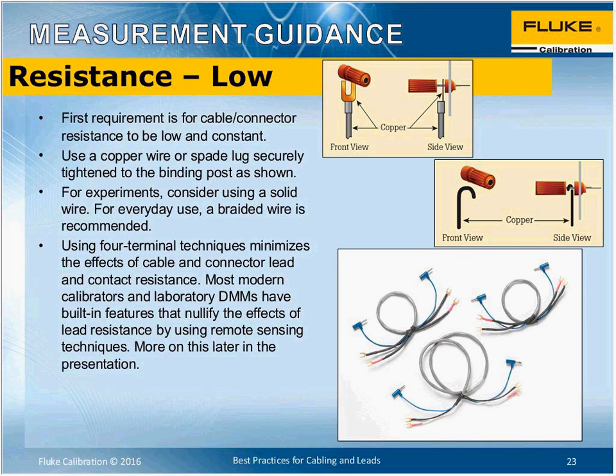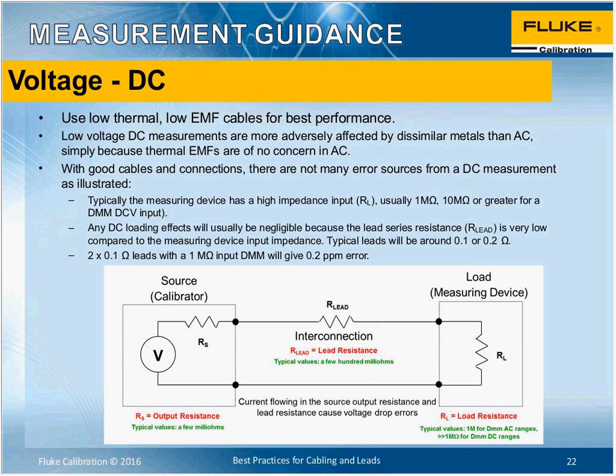But Rich, may I just come in there for a second? Yes, please. Apologies, Paul. There is one thing that occurs to me there. We illustrated that with a calibrator, but if, for example, you were using a voltage divider, it would possibly have quite a high output impedance of tens or even hundreds of kiloohms. The situation might be rather different, but in that case your measuring device would be the dominant impedance. So watch out if you have that situation, and think a little more about what the overall impedance and loading effect is, and leads may or may not be part of that.